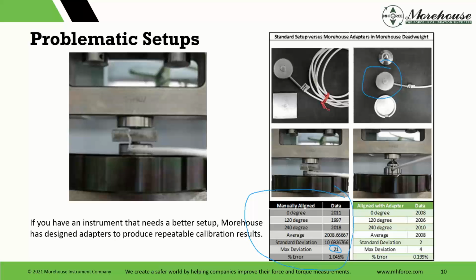Though when we did use the right adapters in here, getting back on, look at the deviation. We went from 21 to 4, and the max error of 1%, we got to 0.2%. Now, the problem with this is, and Patrick's been through these courses, a lot of people expect better than 0.1. Just not going to happen with this type of load cell. So just want to make everybody aware of that.